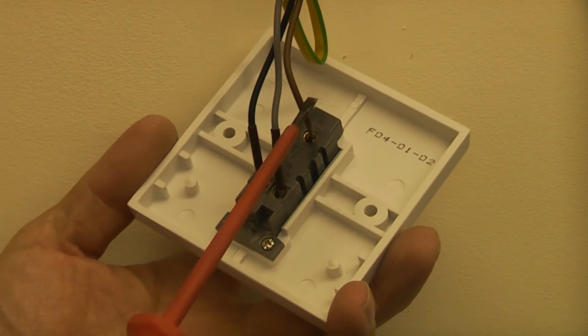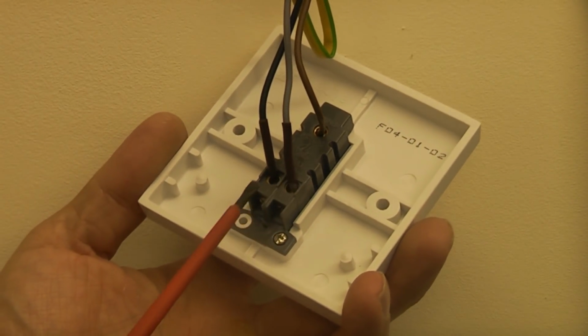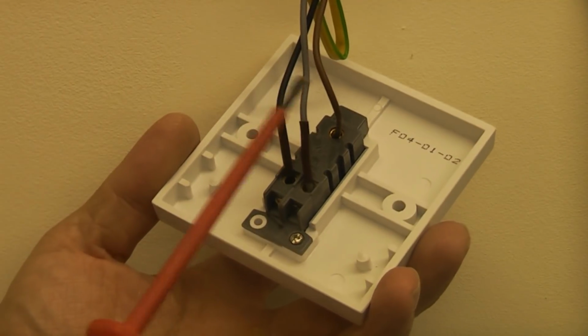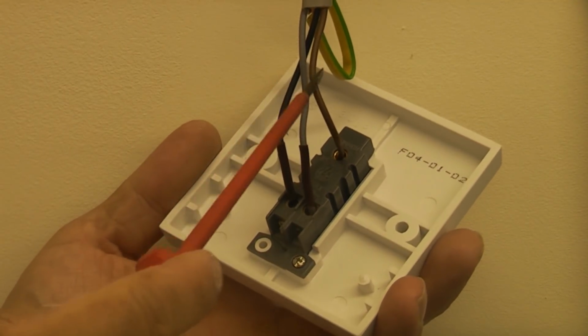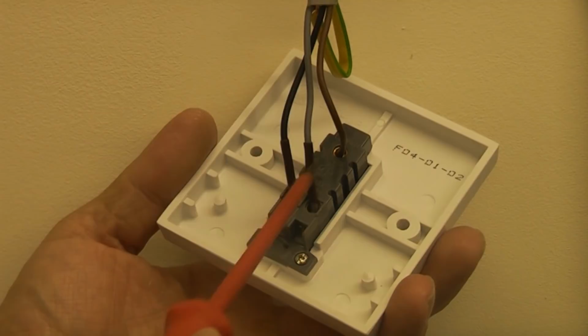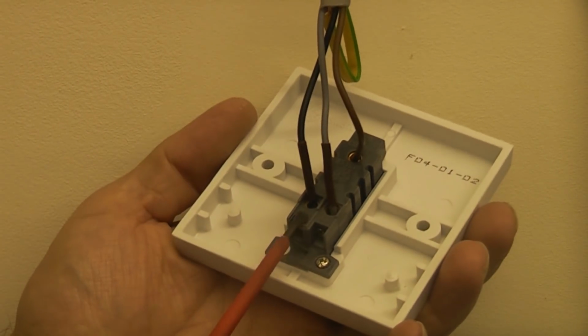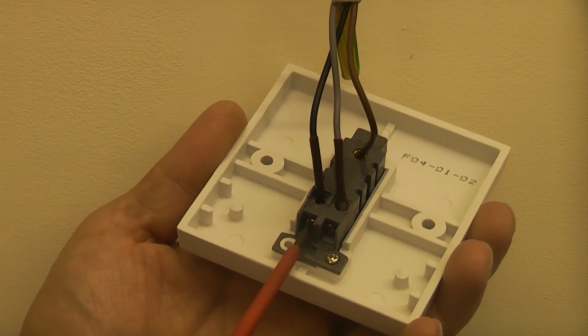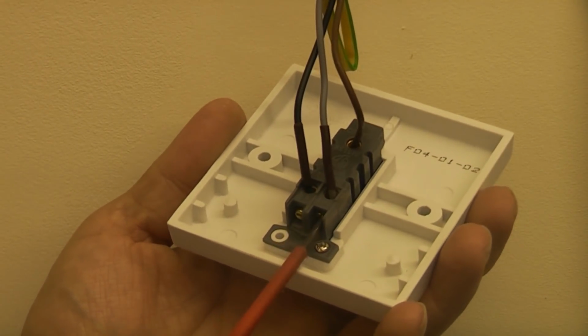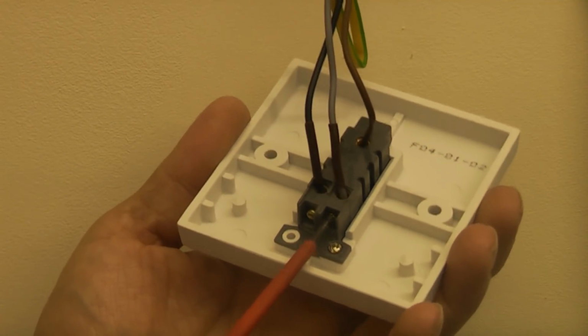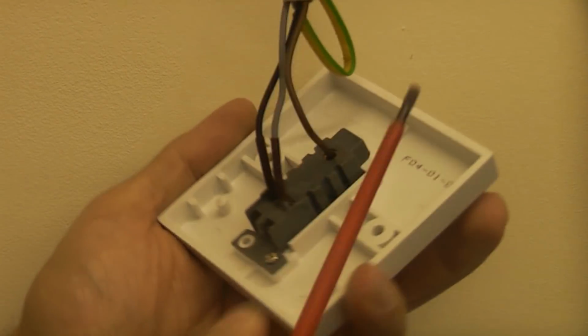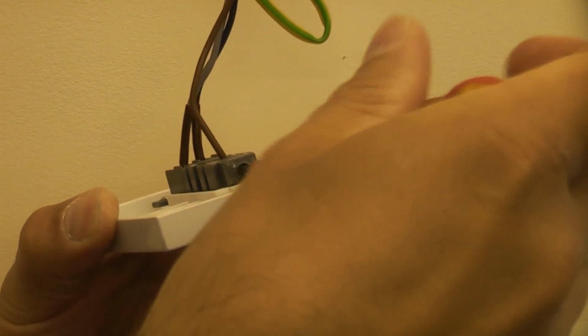So we can see that the brown goes into common, the grey goes into L2 and the black goes into L1. So we need to write that down. If all of your three wires are the same colour, it's important that you label these up with some masking tape before you remove any of them. We can now undo the terminals. And then we can remove the switch.